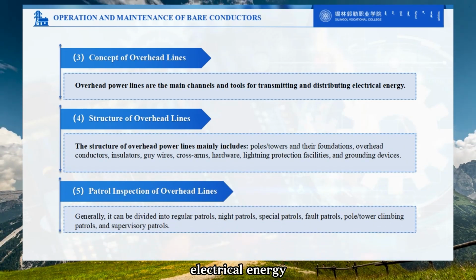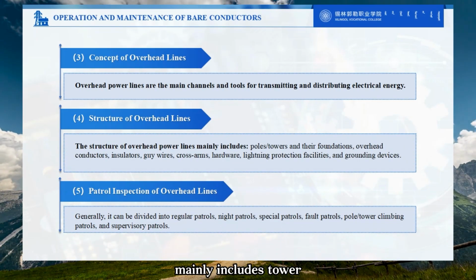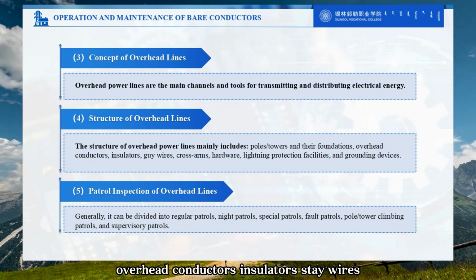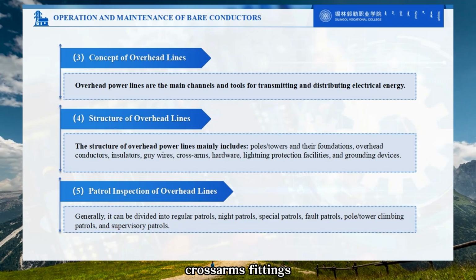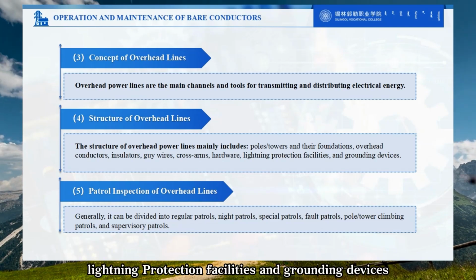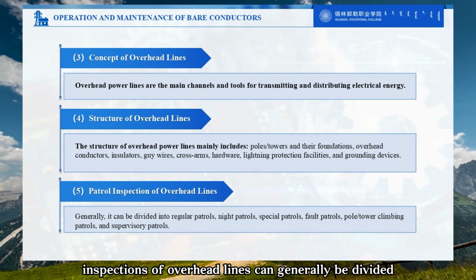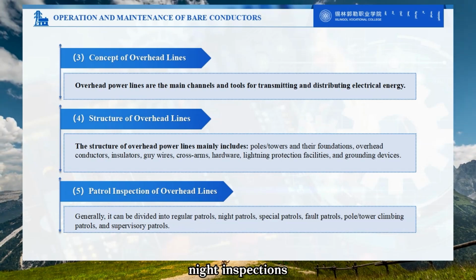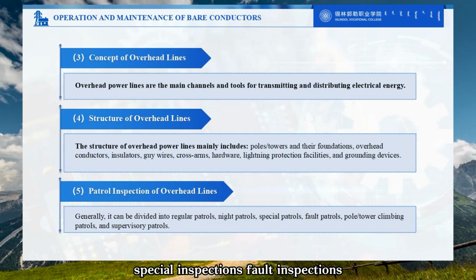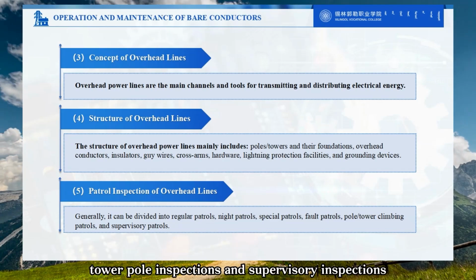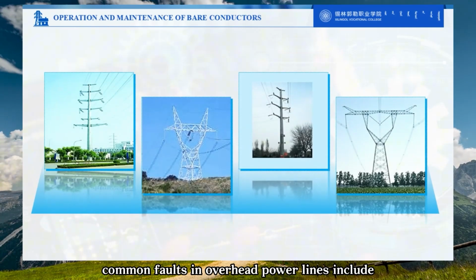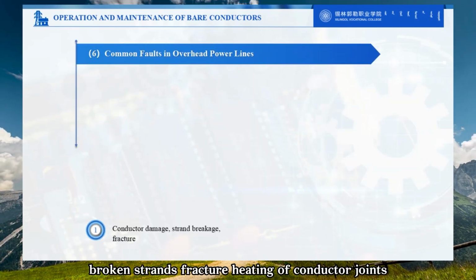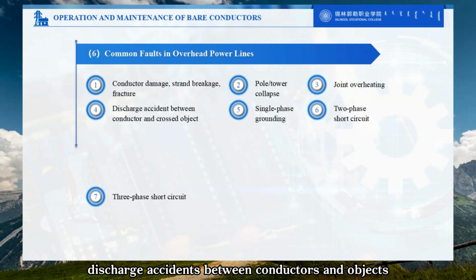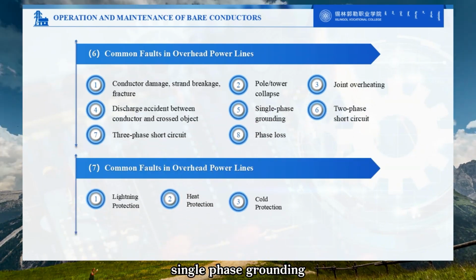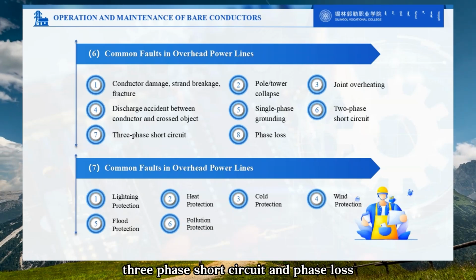Overhead power lines are the main channels and tools for transmitting and distributing electrical energy. The structure of overhead power lines mainly includes towers/poles and their foundations, overhead conductors, insulators, stay wires, crossarms, fittings, lightning protection facilities, and grounding devices. Inspections of overhead lines can generally be divided into regular inspections, night inspections, special inspections, fault inspections, tower/pole inspections, and supervisory inspections. Common faults in overhead power lines include conductor damage, broken strands, fracture, heating of conductor joints, discharge accidents between conductors and objects they cross over, single-phase grounding, two-phase short circuit, three-phase short circuit, and phase loss.